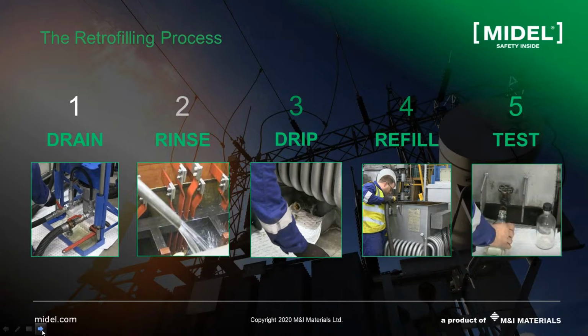And as step 5, we need to carry out some tests. From the transformer point of view, of course, we need to check whether there are any leaks or not. Many times it's possible to carry out the Megger test, or the DC test, or the insulation resistance test. But bear in mind that if you carry out this Megger test, you will get a much lower value than you have with mineral oil. In the case of ester liquids, you will get a value 1/5 or 1/10 lower than you get with mineral oil. That is true for all kinds of ester liquids.